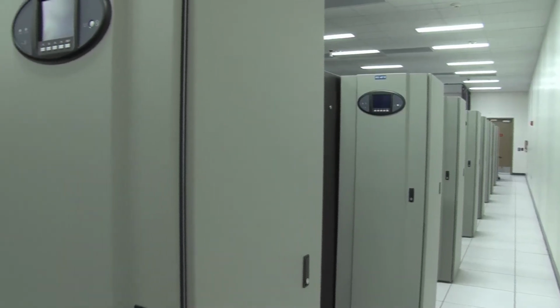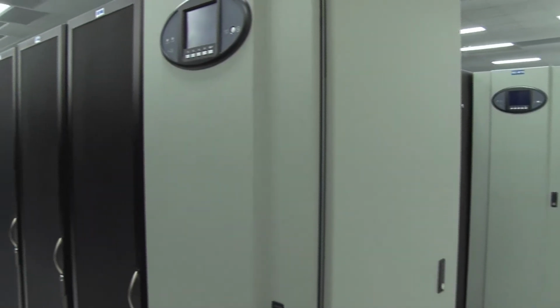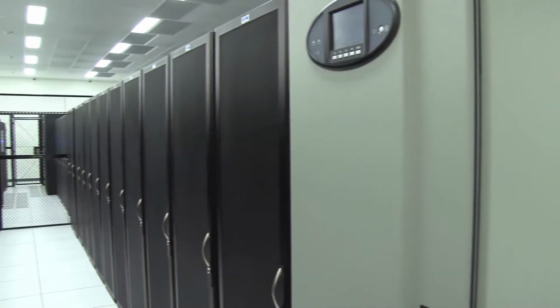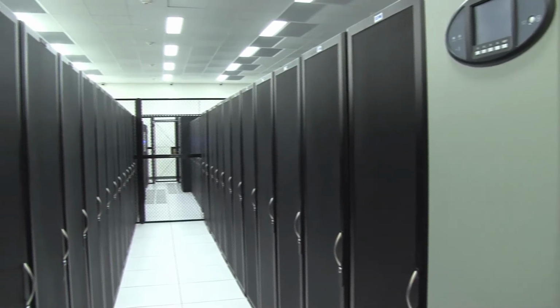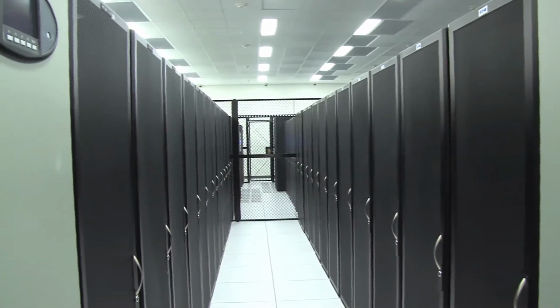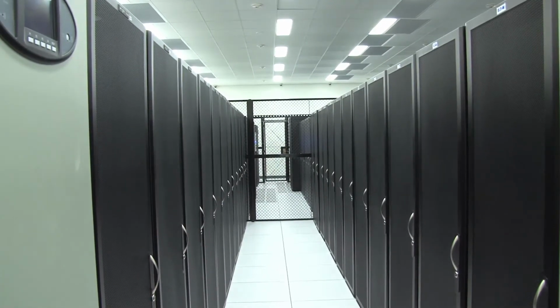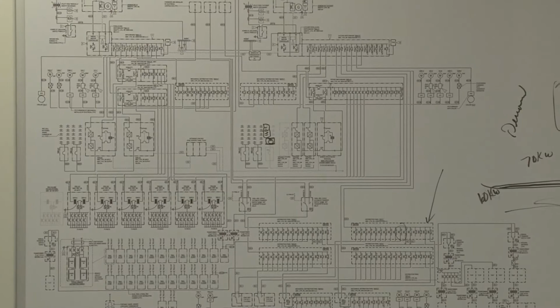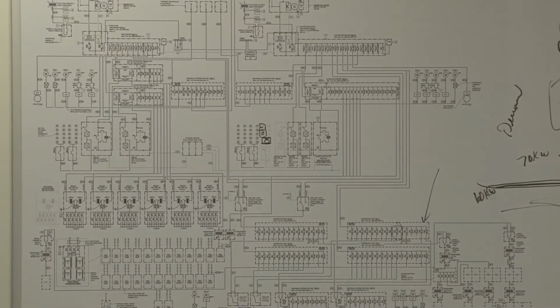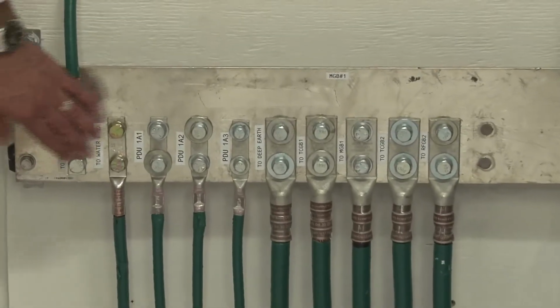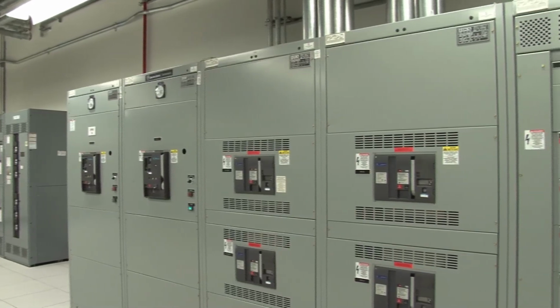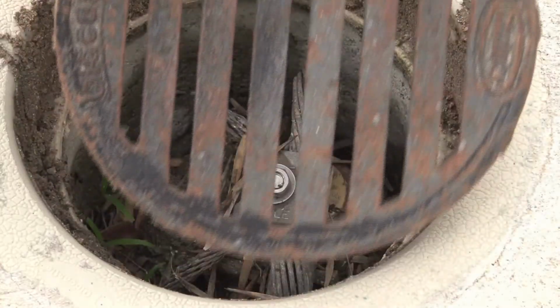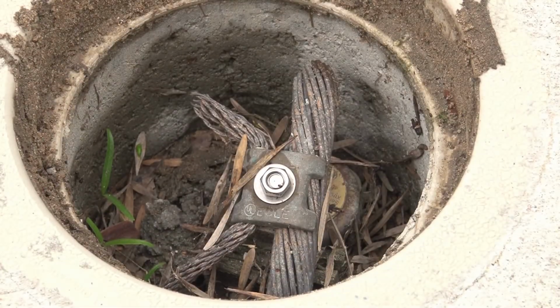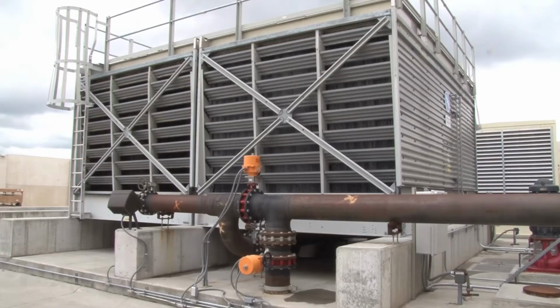CoSentry provides uptime for all of our clients. Most downtime in data centers is human-related. To keep that from happening, we only choose contractors that can abide by the specifications we give. We have commissioning documents, and those documents help us to put together what our annual recommissioning process will be. That includes the grounding. We open up all of our electrical gear, we do infrared tests, we check connections, we check the resistance of grounding electrodes. We also go through all the cooling systems.